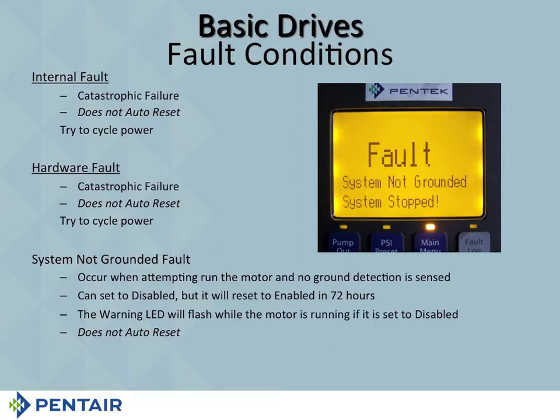You'll know they did that. Don't forget the fan's going to come on, so you'll hear that fan come on. And then have them go ahead and wait 5 minutes. Now, you can stay on the phone with them or you can call them back. It's up to you. Then what you do is you go ahead and you turn the drive back on. If it hits this again, tell them to turn it off. Wait 5 minutes. Call them back. Turn the drive back on. 3 times. If you get 3 faults, they all are the same and they're 5 minutes apart, we know you did your job. That is a warranty.